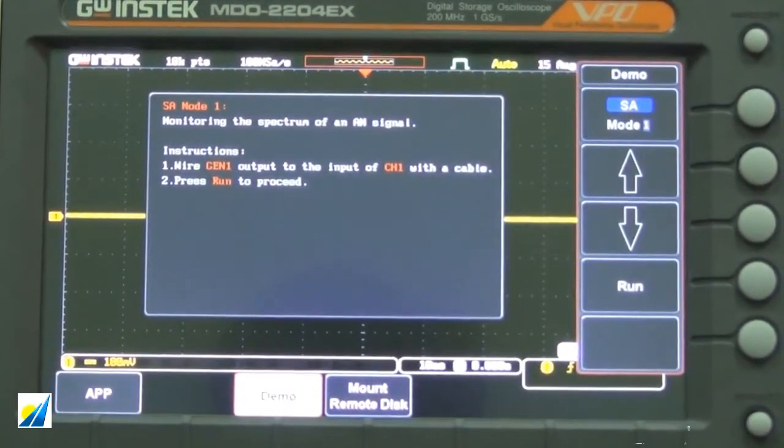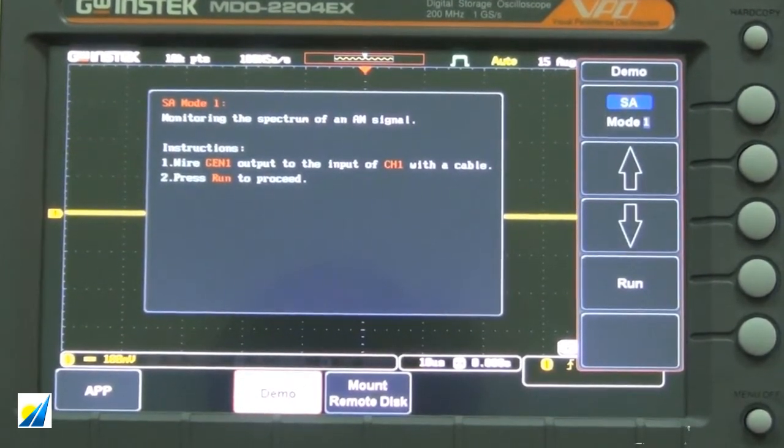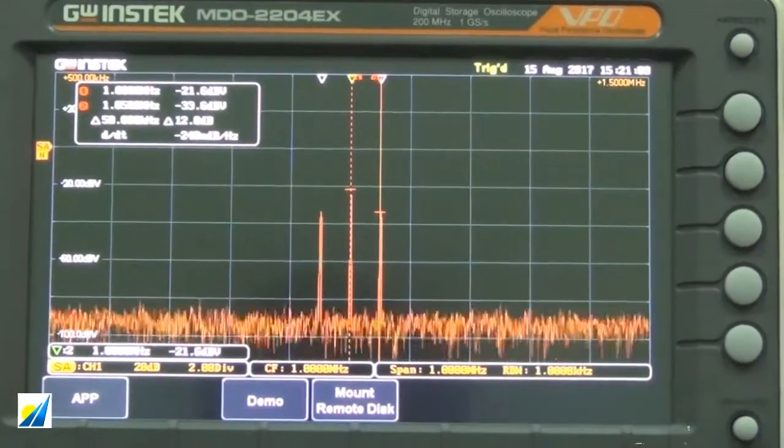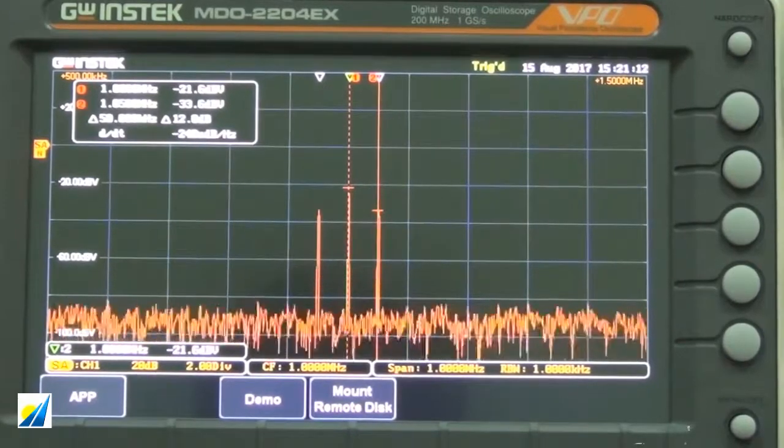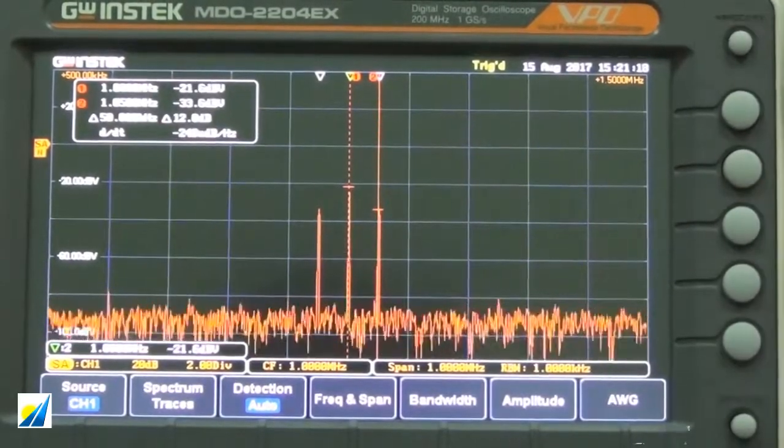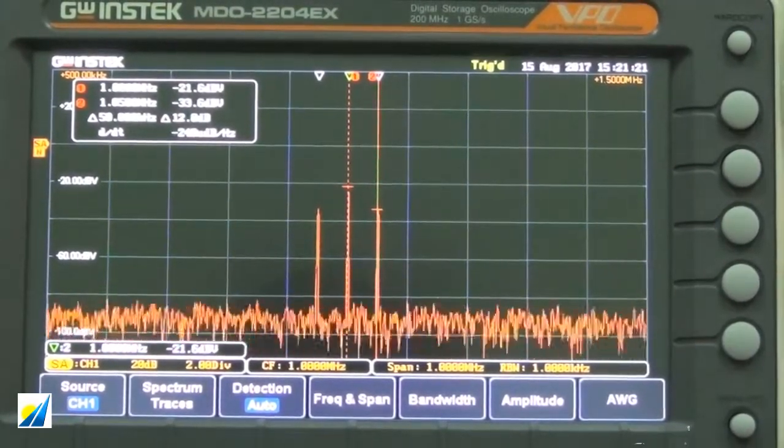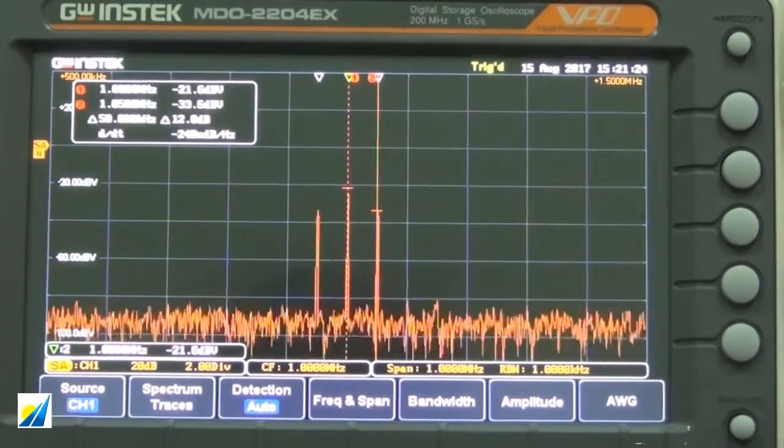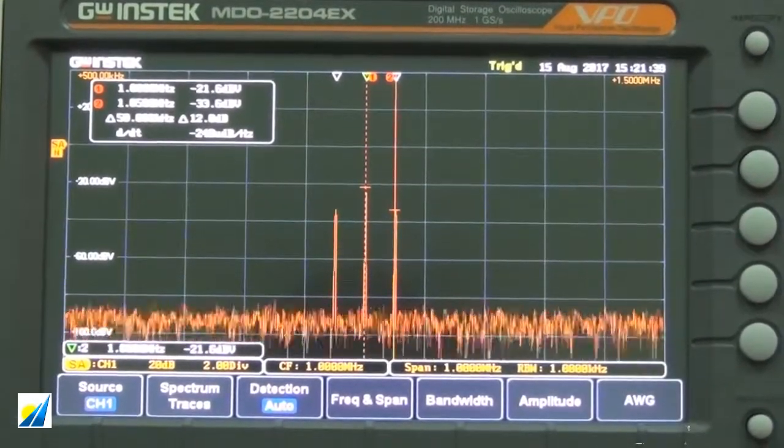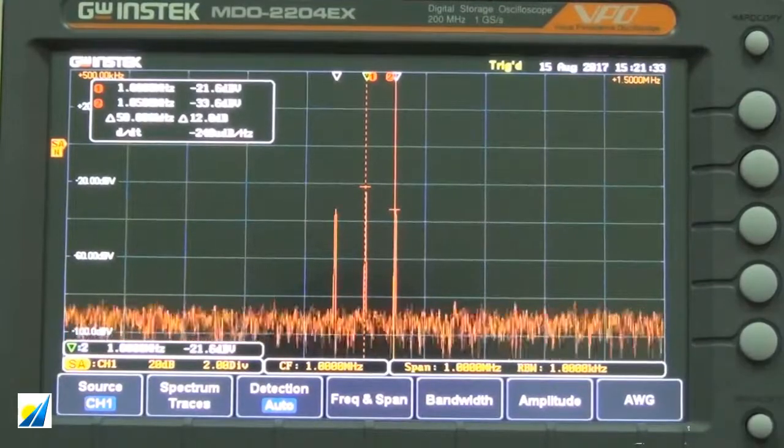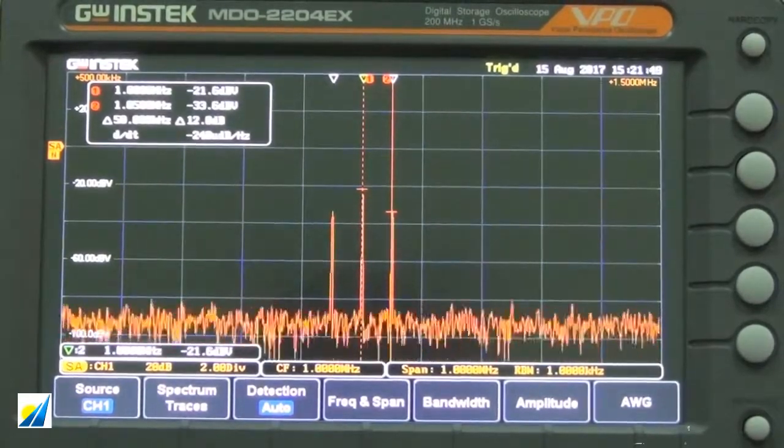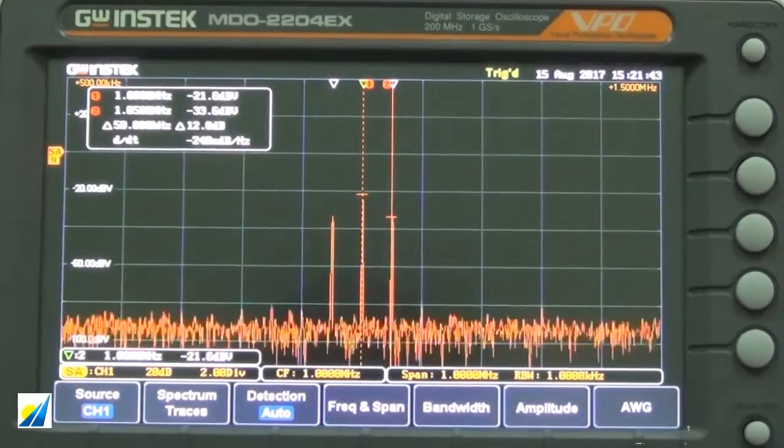First demonstration: Select SA mode 1 and Run. The screen will display AM frequency domain waveforms. Press Option to see Spectrum Settings. This AM signal has a main frequency signal of sine wave, 1MHz, 500mV peak to peak. AM frequency is 50kHz. Demo app has automatically set Start, Stop and Span frequency to correctly display frequency domain waveforms.